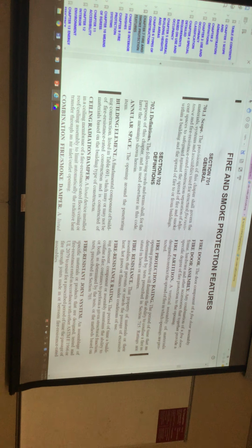It has to be directly connected to an exit. So within the elevator lobby, you come out of the elevator, you're in the lobby, and then you go into the exit enclosure of the stair to get out, or vice versa: come upstairs, get whoever's in that elevator lobby and take them back down the stairs with you. In those cases, they're next to each other, but they're still in separate shafts to have separate protections.